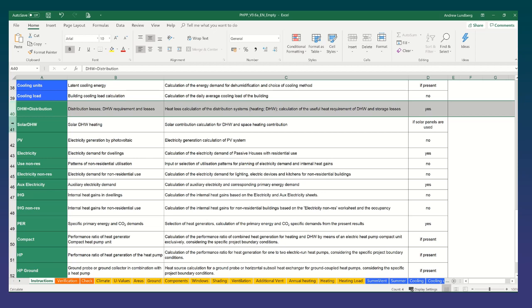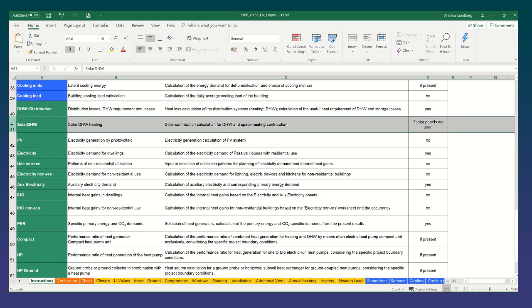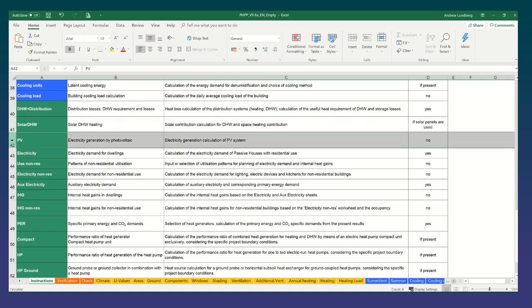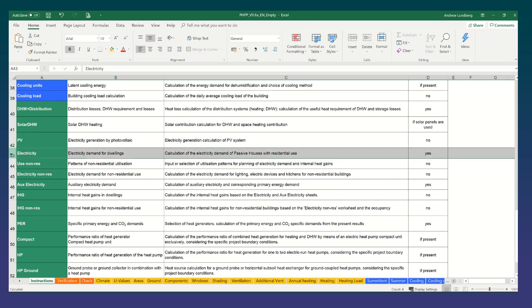The solar domestic hot water tab can be filled in if solar panels are used. They are not a requirement for Passive House, typically only used for domestic hot water. It's difficult to use solar thermal panels for space heating in our climate although the efficiency of panels increases it will become increasingly possible. What's becoming more popular is the use of PV particularly in determining Part L compliance with building regulations and use of PV as a renewable to offset primary energy consumption values and a technology being used quite often now is photovoltaic panels that have a re-diverter once the batteries are being recharged or depending on whether it's got a grid connection to actually heat up an immersion cylinder first before actually diverts power anywhere else so it's actually a PV supporting domestic hot water.